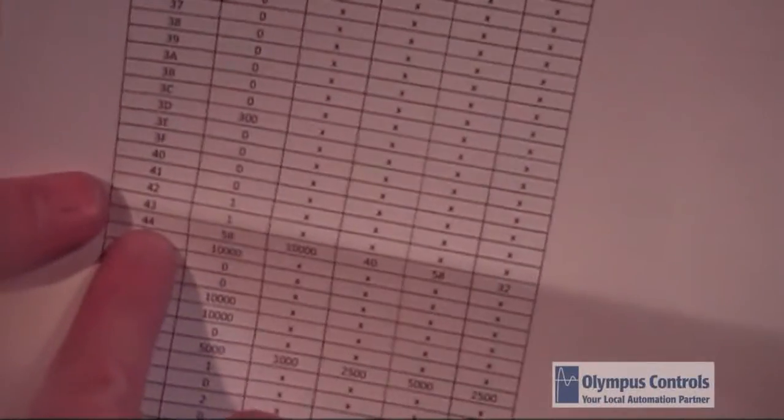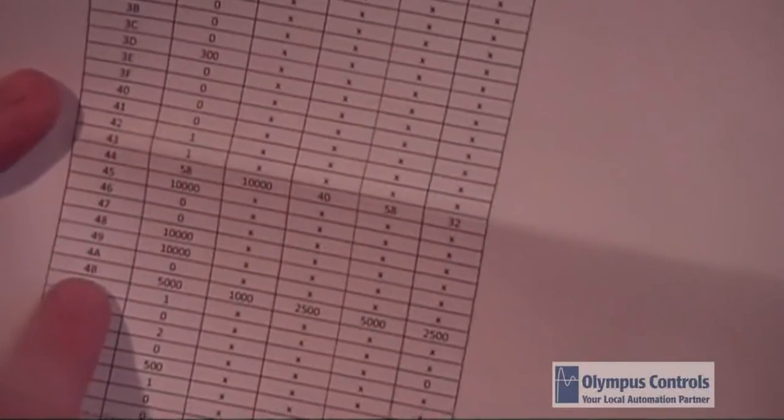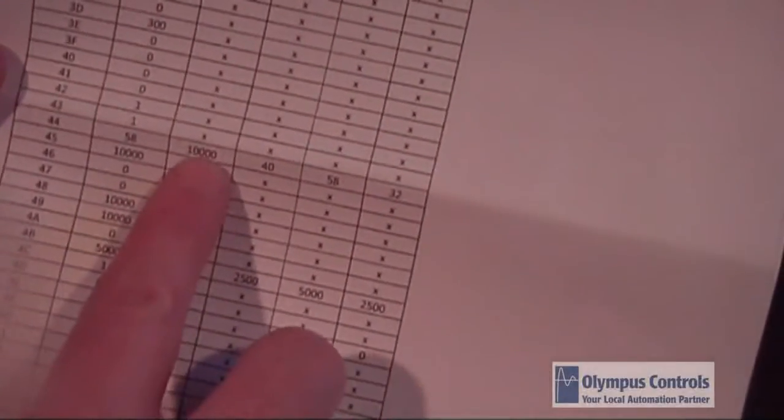If now we want to change to a cutter axis, we'll see here on page 2 that parameter 46 and parameter 4B require changes to 10,000 and 1,000. Other than that, there are no changes required in this drive to be configured as a cutter. So I'll now show you how to do that.